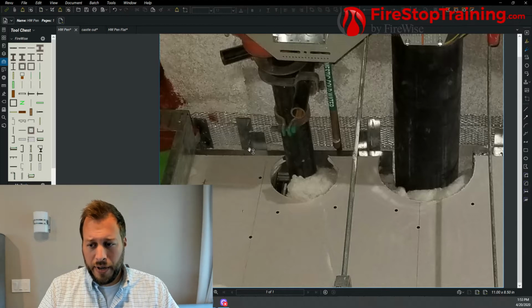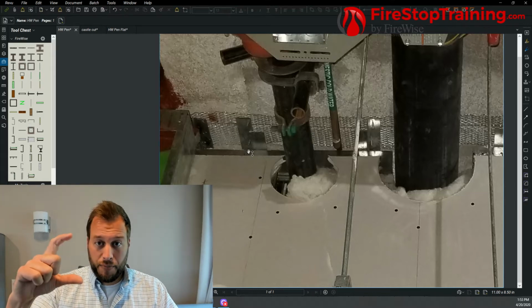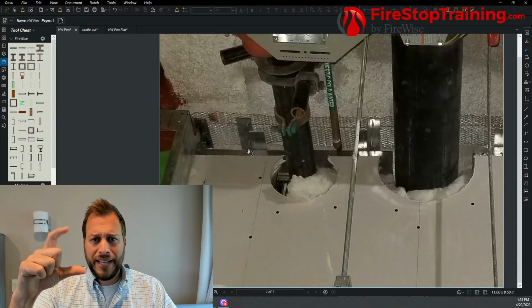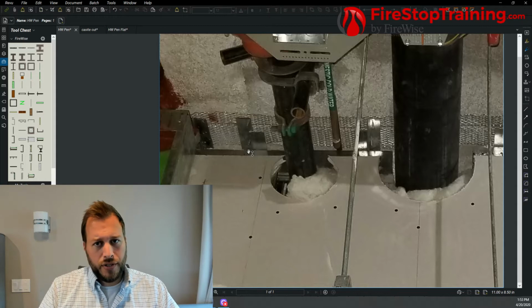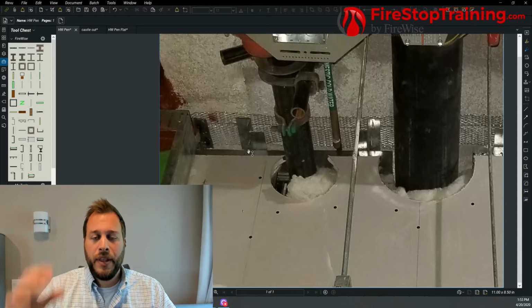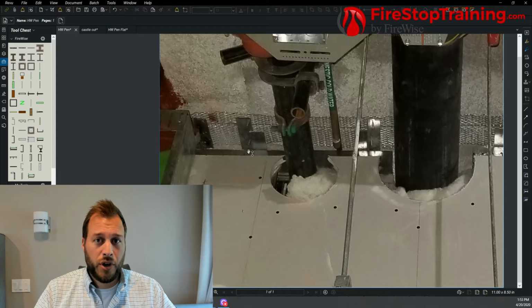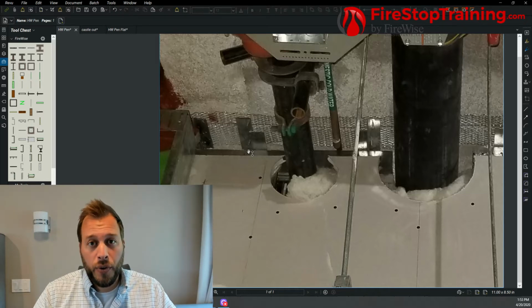Wall joints, fire rated joints at the head of wall like this, actually have the option in their test standard in the building code to be tested for compression or extension, so the wall going up and down, so they can test how the fire stop works in that movement. Penetrations, by code, do not require a movement test to see how the pipe moves in and out or up or down. There is now an ASTM standard that manufacturers are just now starting to learn and play around with a little bit, but it is not in the code.